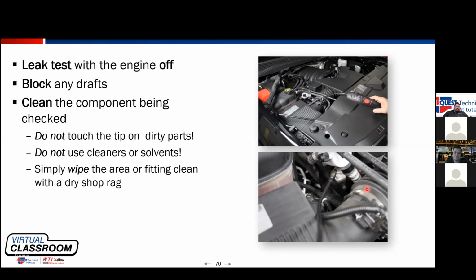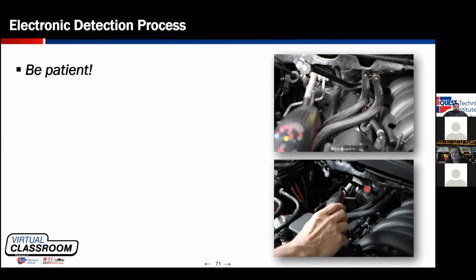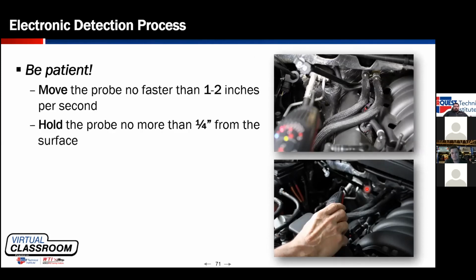Using a clean, dry, lint-free rag is a great way. You wipe it off, a little bit of water if you need to. Make sure that it's dry, and then go do your leak detection. The number one thing with electronic leak detection is patience. Guys tend to move too quickly. The standard says to move at 1 to 2 inches per second. To me, that's a little bit fast. You have to give the leak detector time to find the leak, time for that refrigerant to get from the tip, where the component is, up into the sensing element and to register the leak. So we said no more than 1 to 2 inches per second.